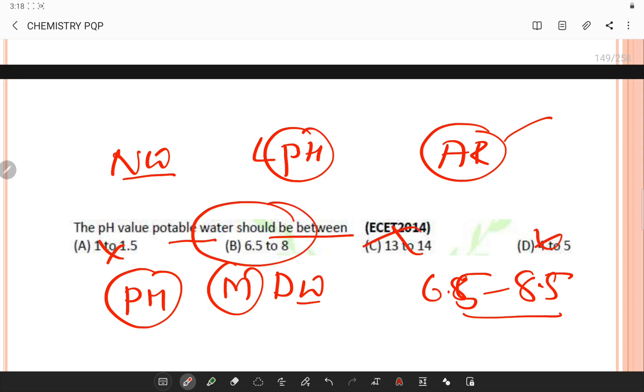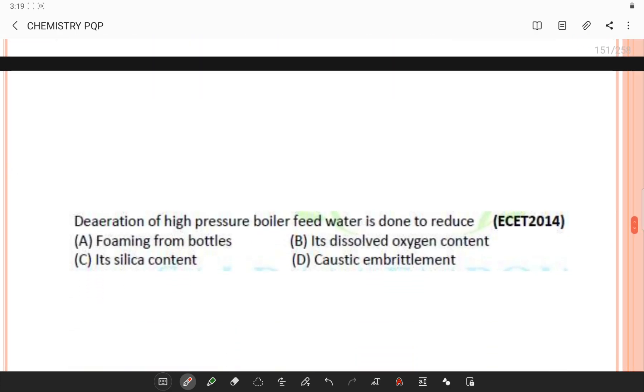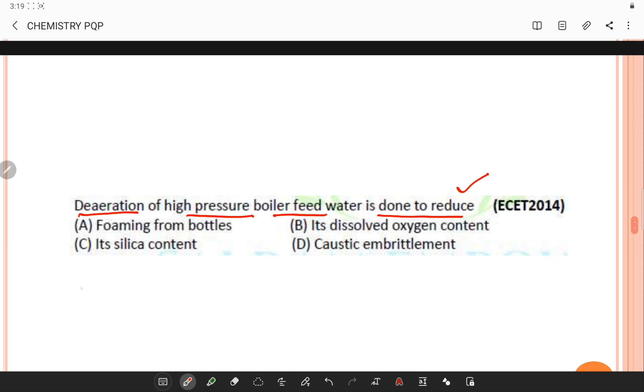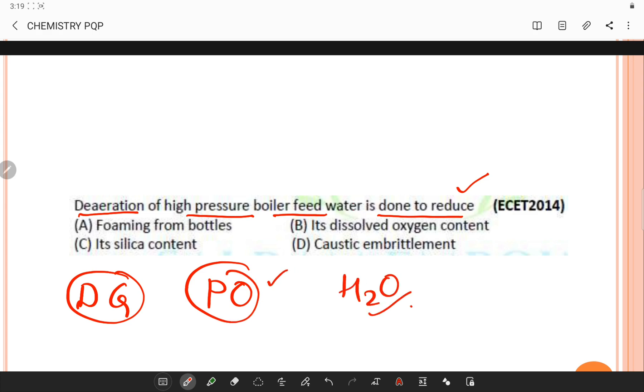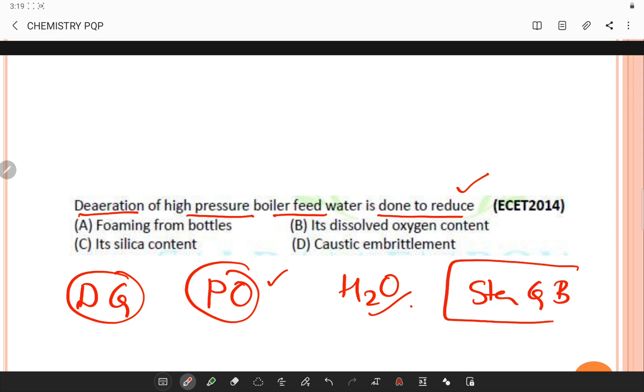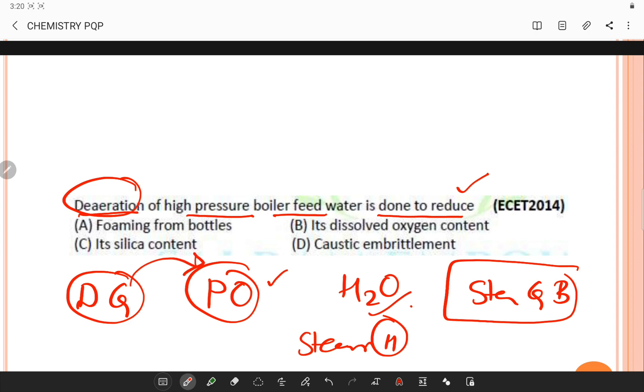De-aeration of high-pressure boiler feed water is done to reduce dissolved gases — in particular, dissolved oxygen. De-aeration is used to expel dissolved gases from water prior to its use in steam-generating boilers, and is usually accomplished by steam heating. Dissolved gases in water cause corrosion in the boiler, condensate, and feed water system. So de-aeration primarily removes dissolved oxygen content.